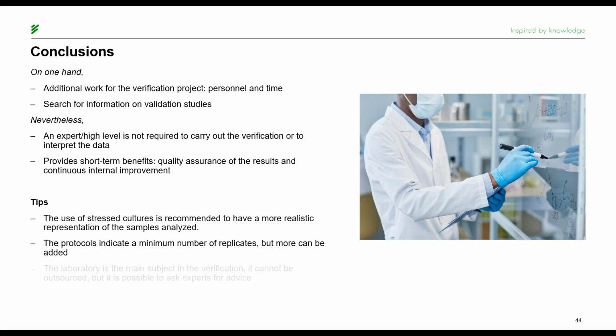So what advice can we give for the verification beyond what we've seen? Well, again, the recommendation of using stressed cultures to have a more realistic representation of the samples analyzed daily in our lab. The protocols indicate a minimum of replicas, but it would be ideal to add more to make our verification more robust. And although the only one that can carry out the verification is the laboratory, it is not possible to outsource this process. It is possible to ask for advice or help from experts in the field.